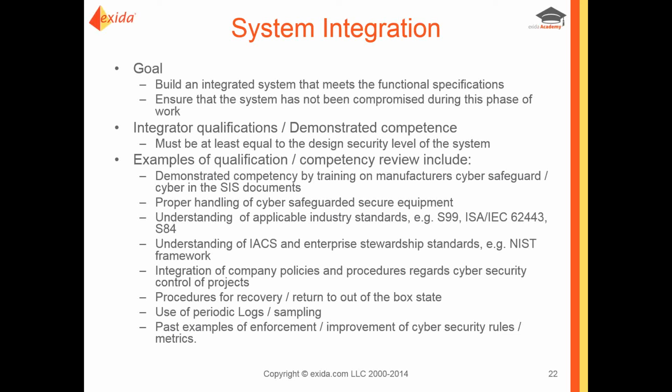And here we've got a list of qualification and competency review items that you can take a look at. You want to see if they've trained their personnel. You want to see if they've got proper handling of cyber safeguarded equipment. Do they understand the applicable industry standards? Do they also understand some of the enterprise stewardship standards in the area of cybersecurity? One example is the NIST framework. You can actually use the NIST framework to audit the fabricator to see how well they stack up.